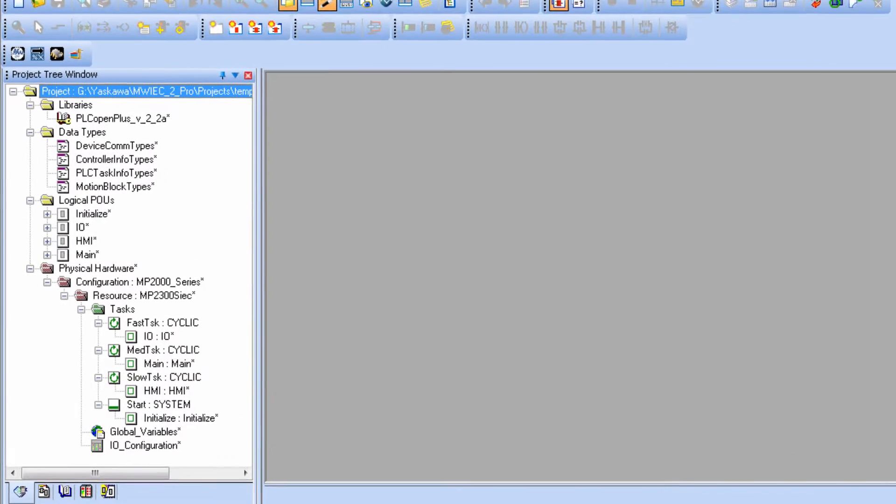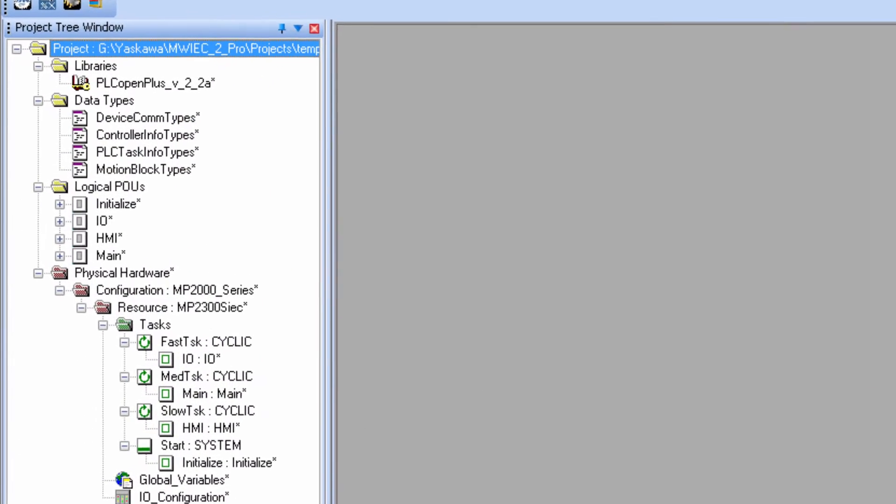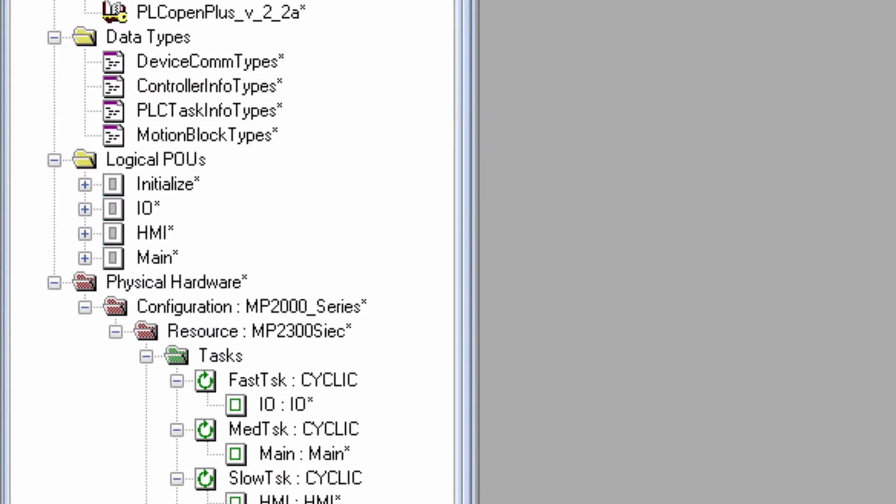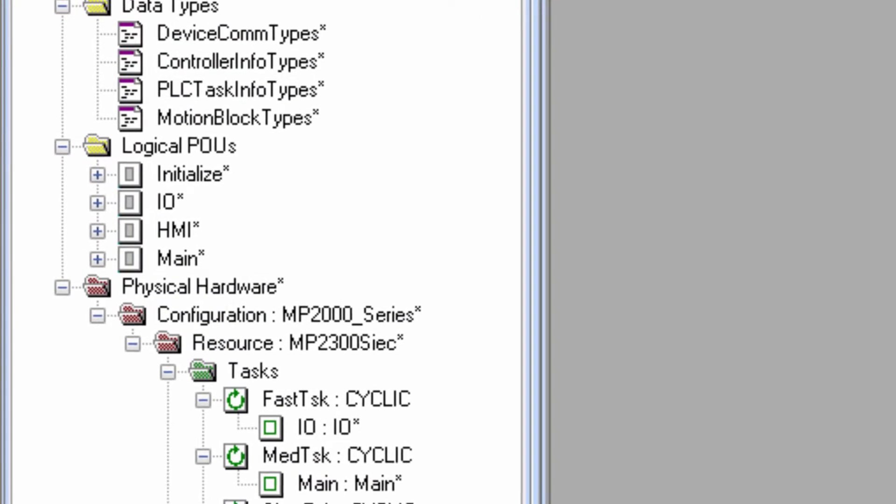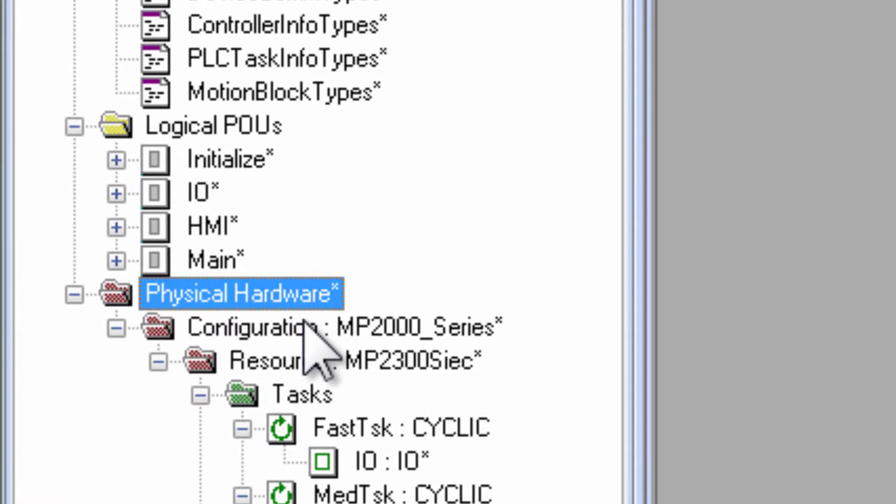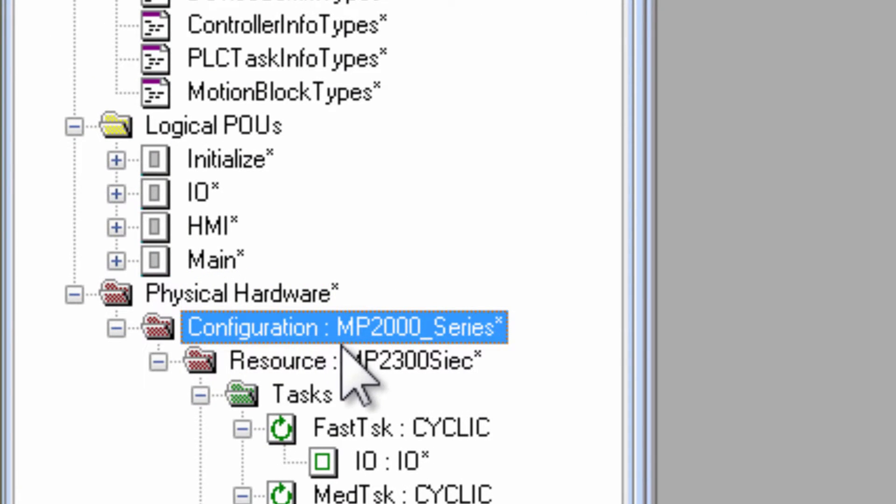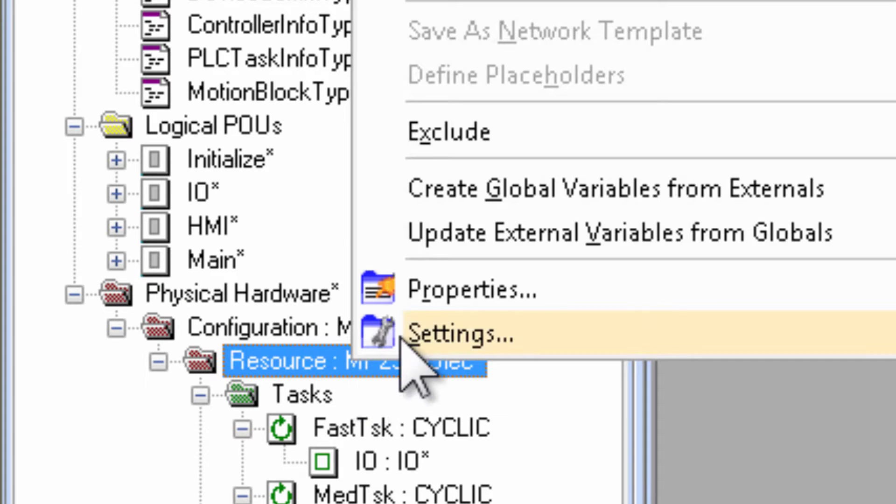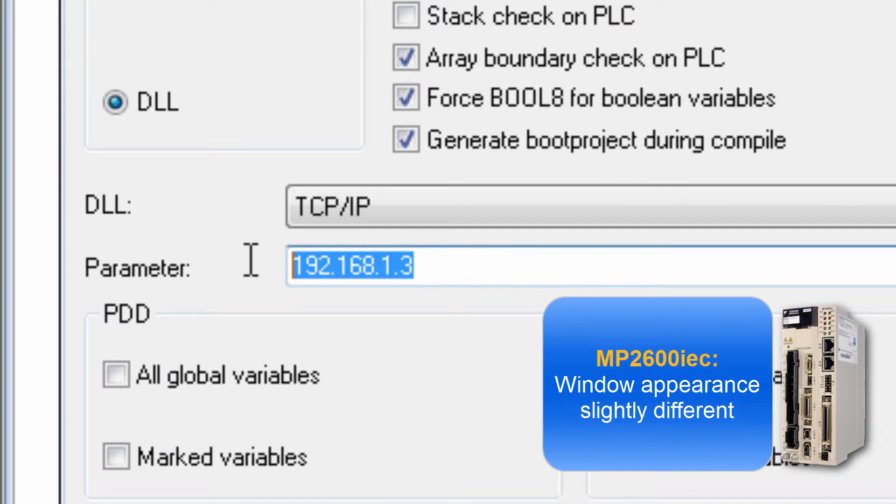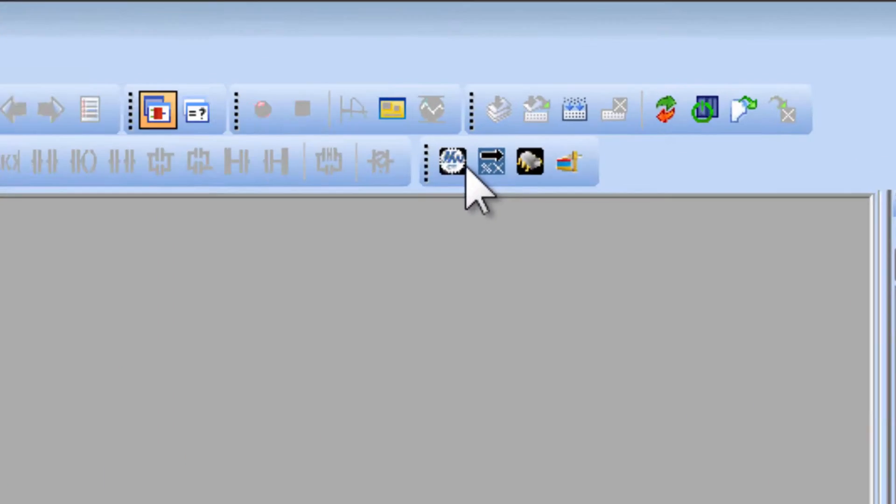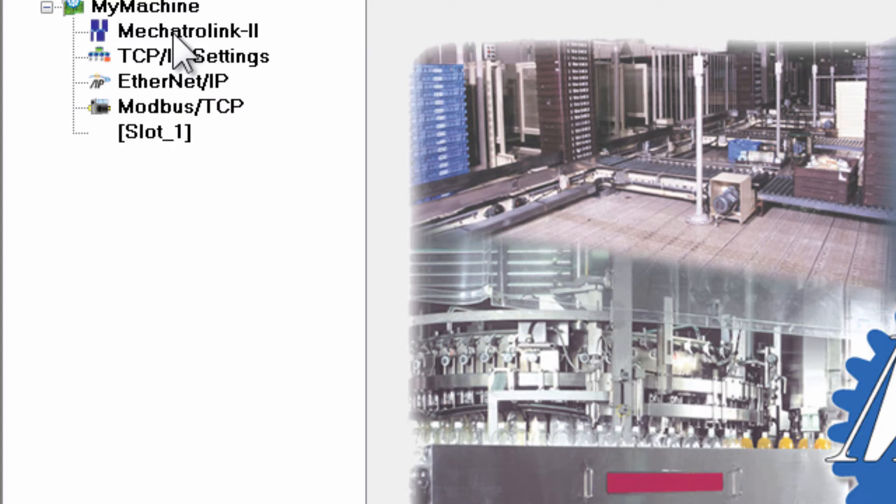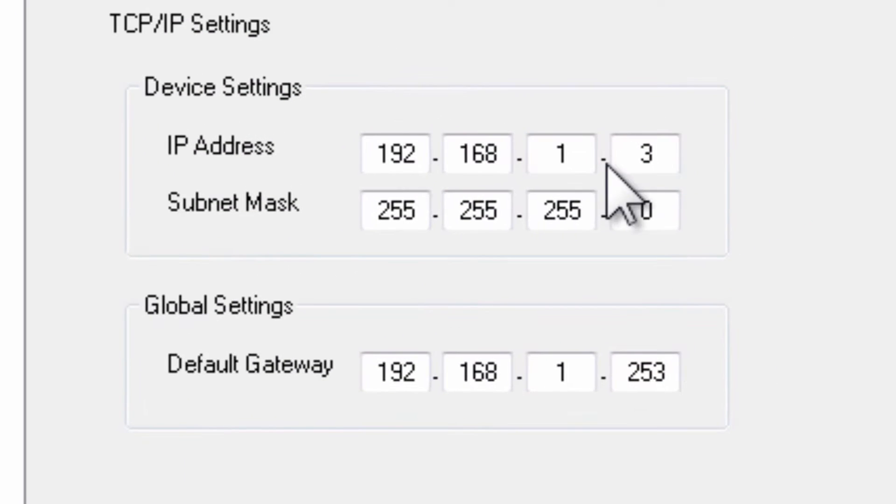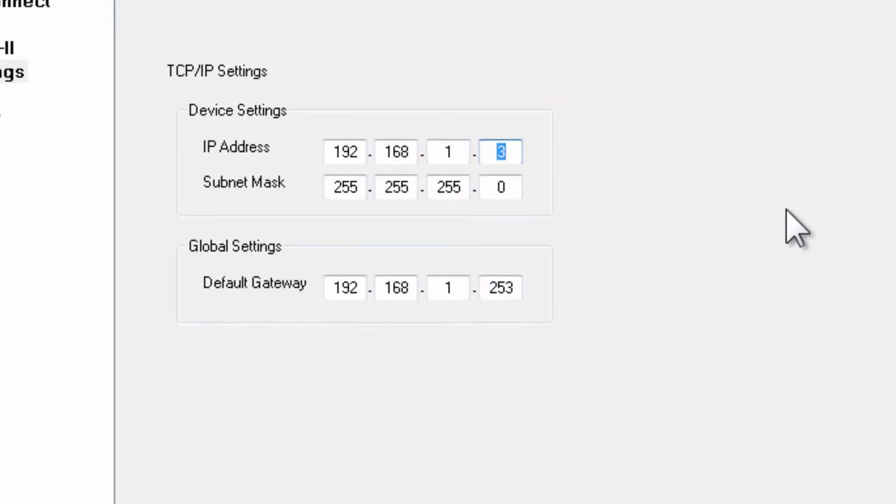If you have the MotionWorks IEC project for the controller, the IP address can be seen in the project tree under Physical Hardware. Right-click Resource and choose Settings. The Hardware Configuration TCP/IP settings also show the IP address expected for this project.